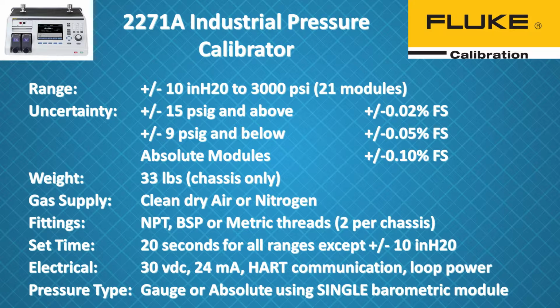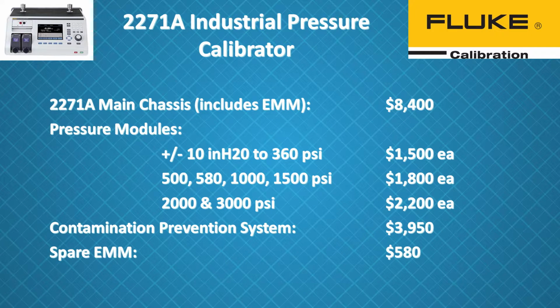And there's 2 test ports on the top of each unit, as you saw. The pressure set time is 20 seconds for all the ranges except for the plus or minus 10-inch module, so very quick to set and stabilize pressure. Electrically, 30-volt DC input, 24 milliamps, HART communication, and it does provide loop power as part of that EMM module. Pressure types can do gauge or absolute using a single barometric module. So if you buy one of the barometric modules and install it inside in one of the slots in the 2271A, then you can take your gauge pressure modules and do any combination of gauge or absolute pressures up to the max of that module. As far as pricing goes on the 2271A, the main chassis itself, including the electrical module, is $8,400.